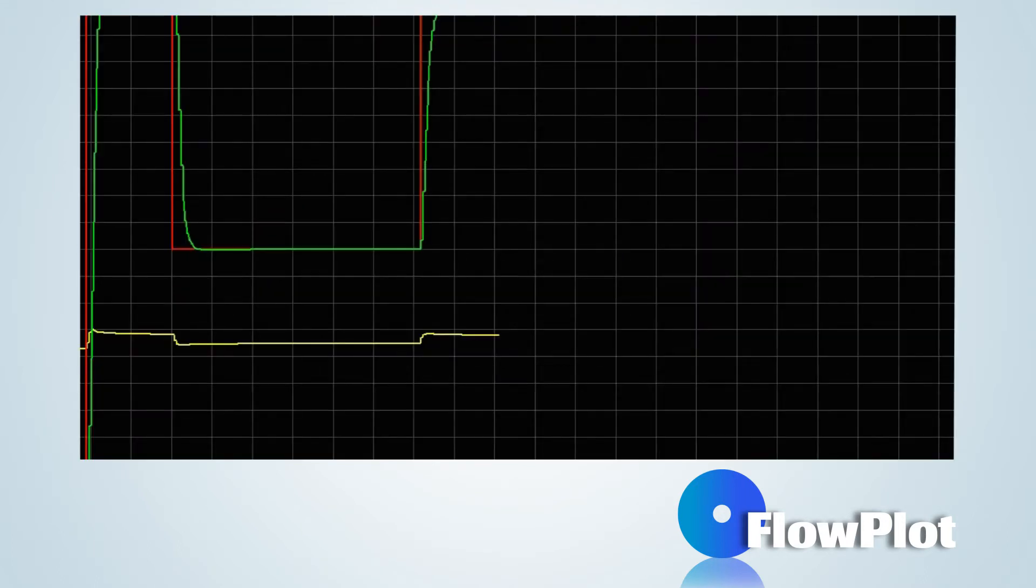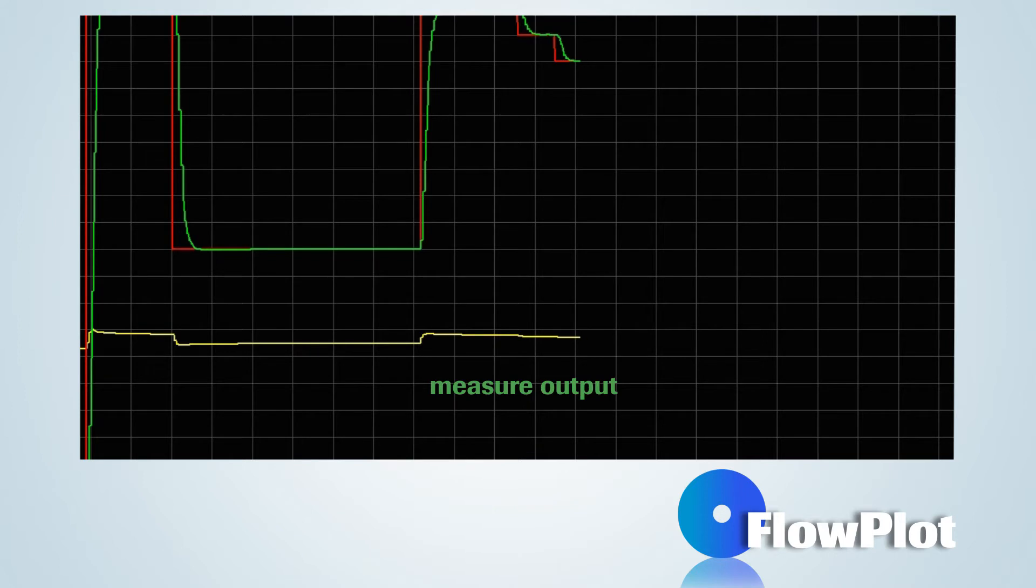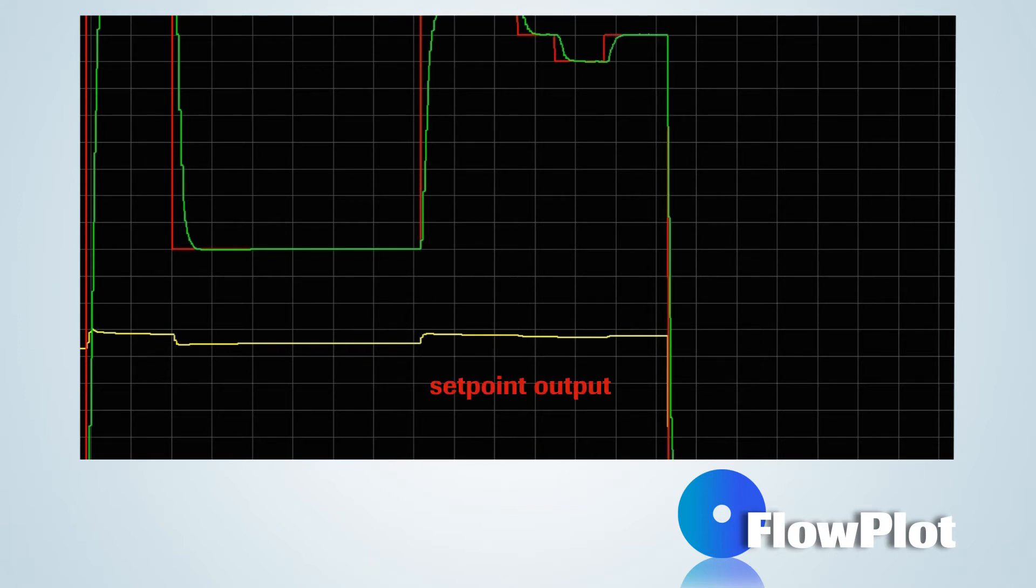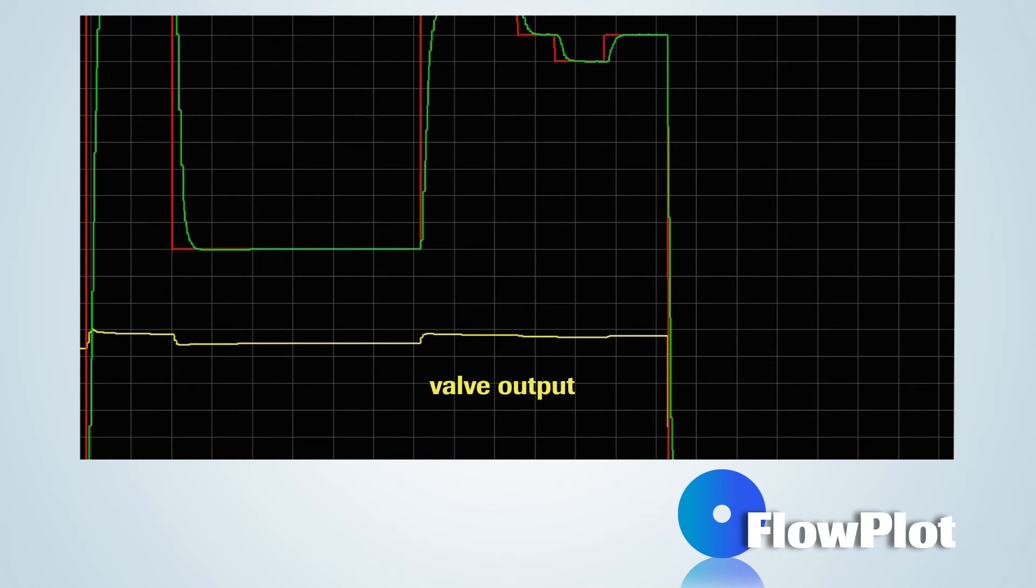In this example, the green plot line represents the measure output. The red plot line, the setpoint output. And the yellow plot line, the valve output.